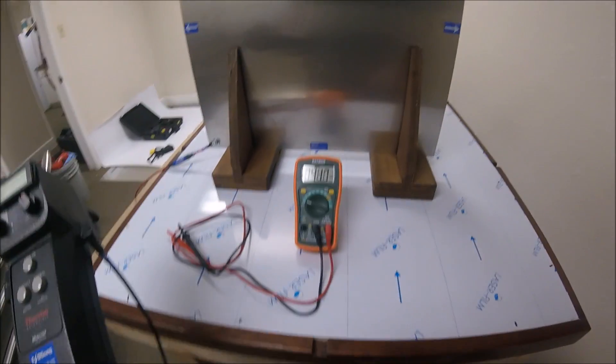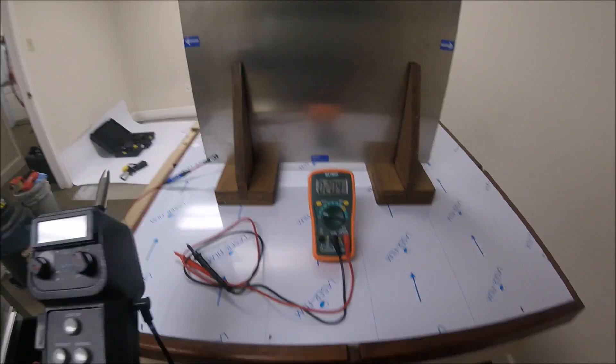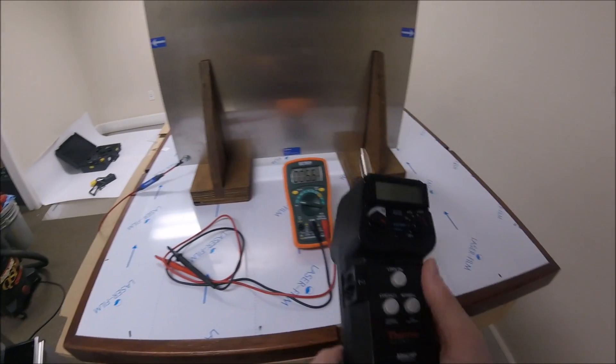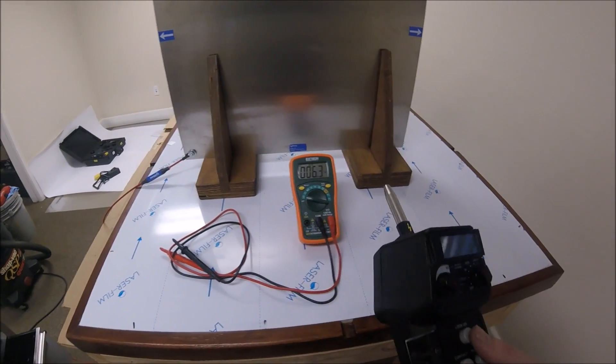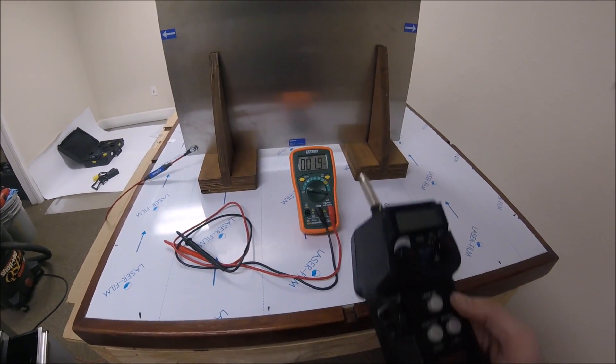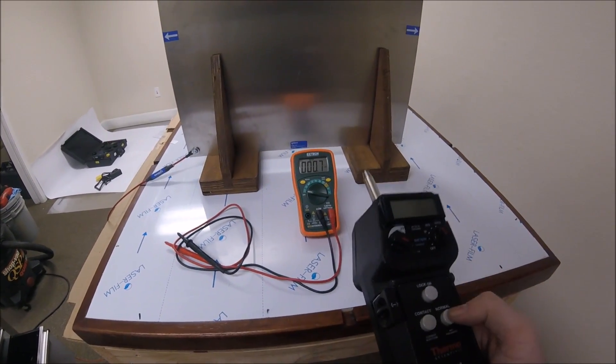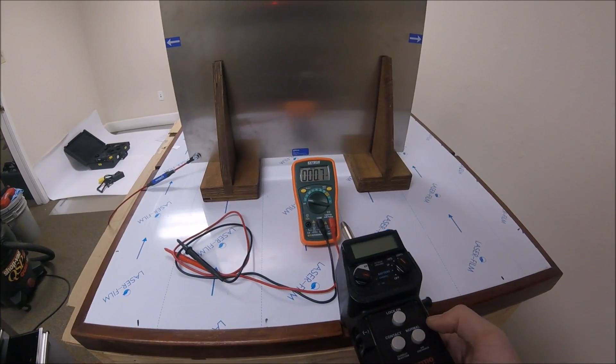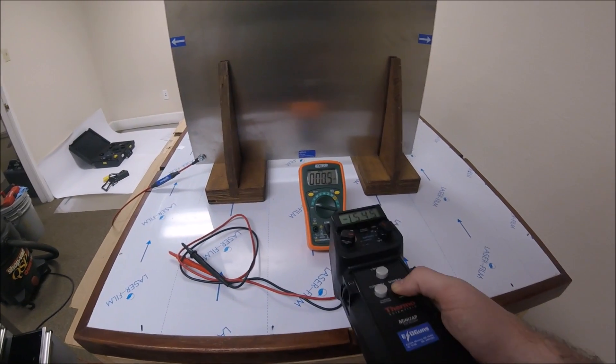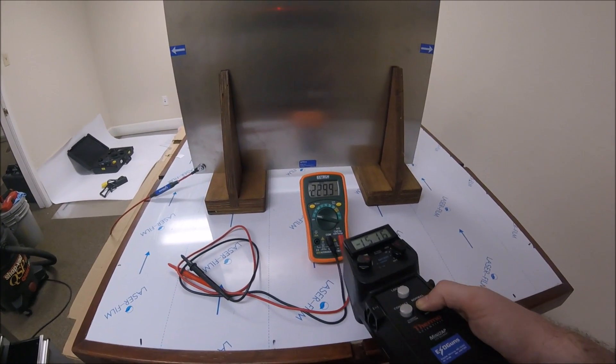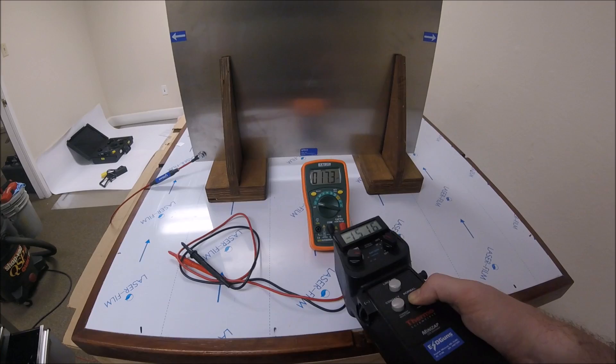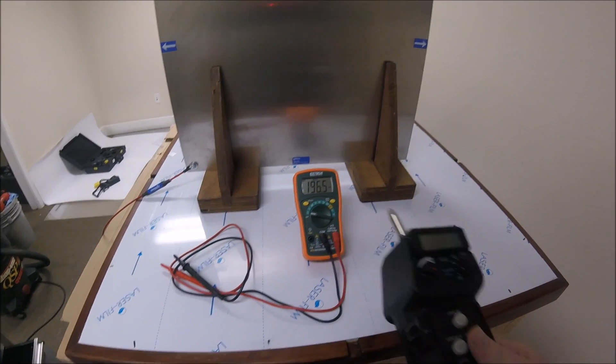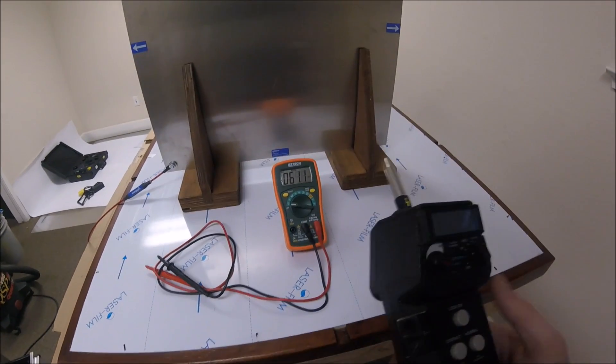Alright, now that we have the unit grounded, power knob to 1 pulse per second, voltage knob maxed out at 15 KV, which represent level 4 of the air discharge requirements in the standard, I'll probe which should be done at a higher frequency, but when I tried it with this multimeter it goes into overload.